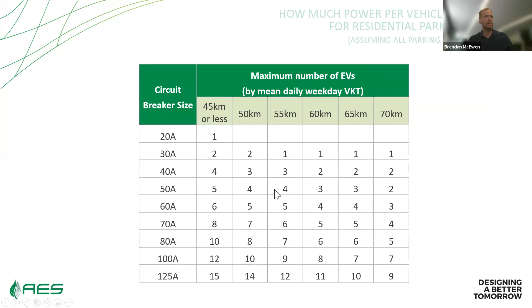It's worth comparing that 4-share on 40 amp circuits to what's currently in the Toronto Green Standard version 3. Right now version 3 says charging systems must supply a minimum of 16 kilowatt-hours per EVSE over an 8-hour period if all parking spaces are in use, which allows for 3-share on 40 amps or 6-share on 80 amps. We're saying it's actually possible to provide really good quality charging while allowing more sharing—this would be the maximum extent of sharing we'd recommend.